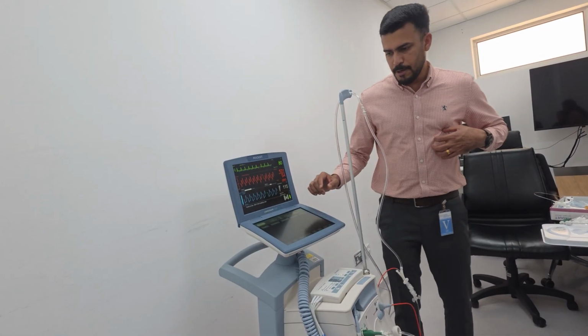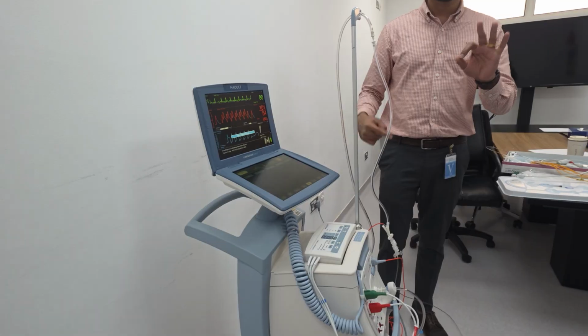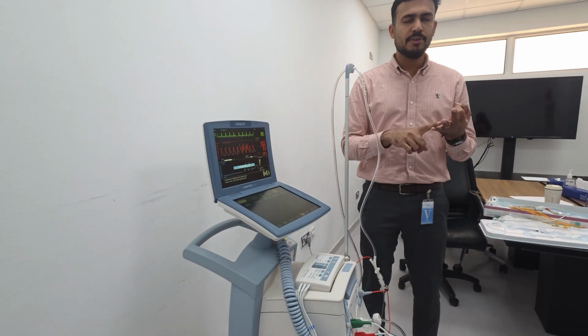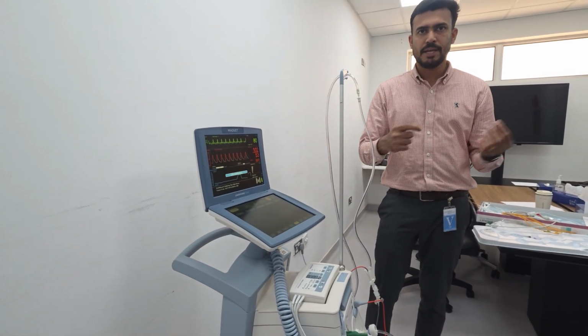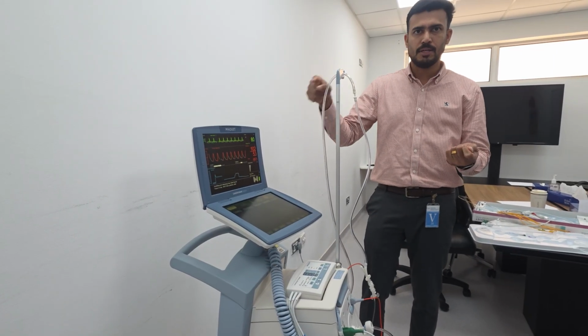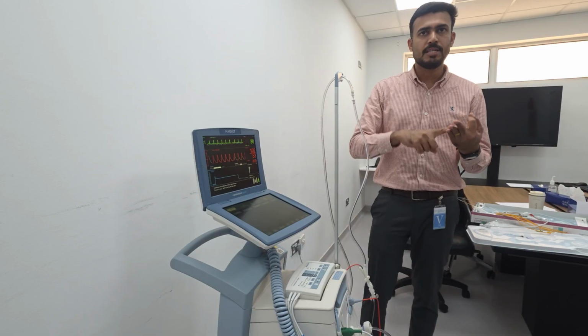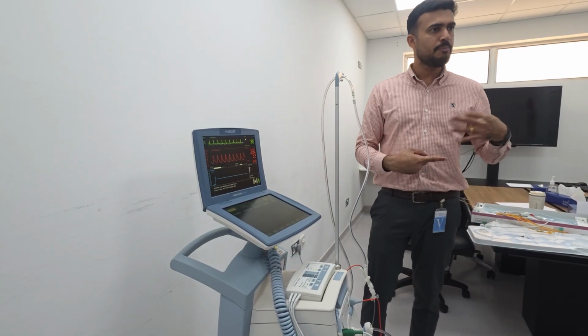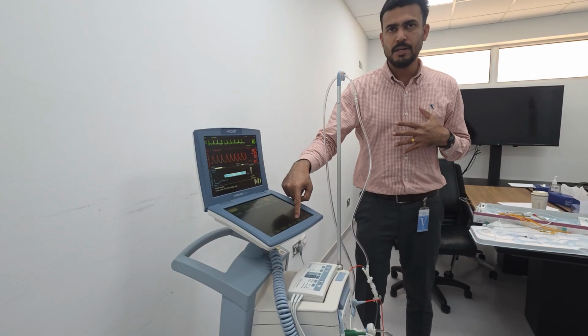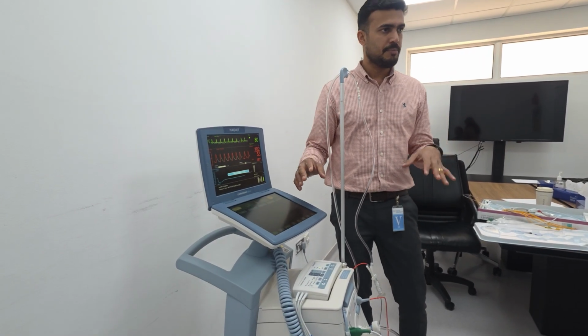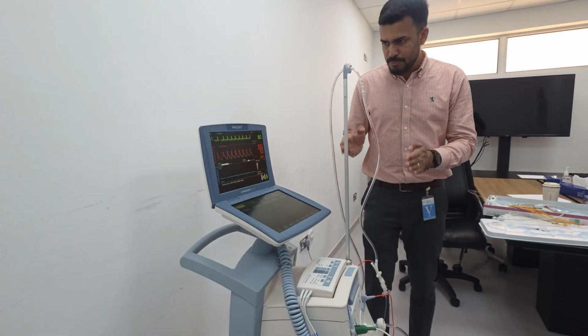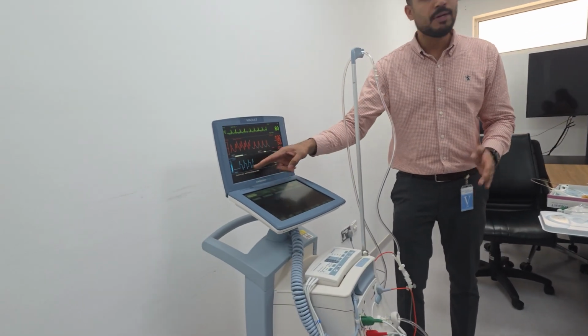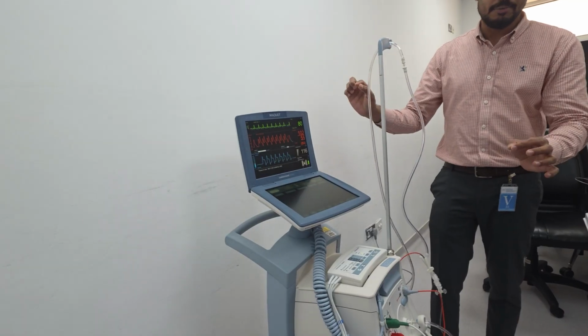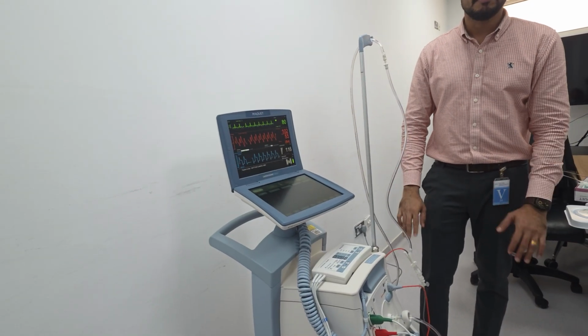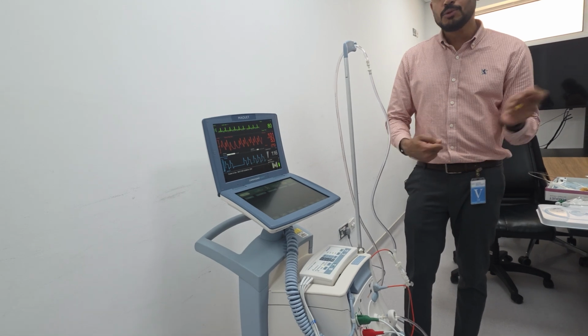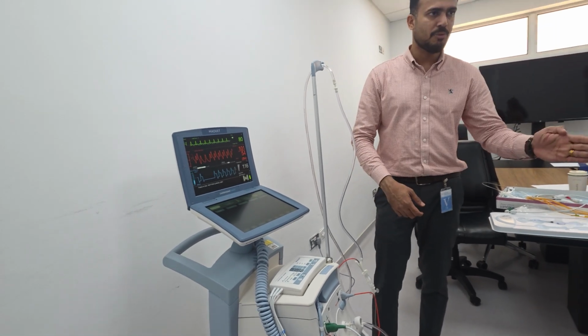Okay. Now, before changing the cylinder, you can fill it. Or whenever you find catheter alarms, fill it before using it. So you can see it will do a deep vacuum. You can see blood is coming out. Okay. And the third one, which I told you: if the patient temperature is high and you are getting continuous leakage alarms only because of the patient temperature differences, then you can initiate an autofill every 1 hour. Okay. So autofill complete. Start. Now from this moment, the machine will initiate a normal autofill after 2 hours, unless a disconnection happens. Okay. So you can change your cylinder, to avoid the autofill procedure happening while changing the cylinder. So you are initiating it just before that.